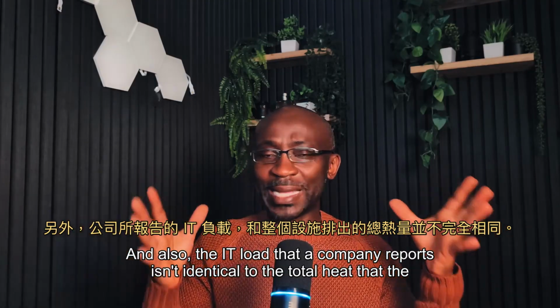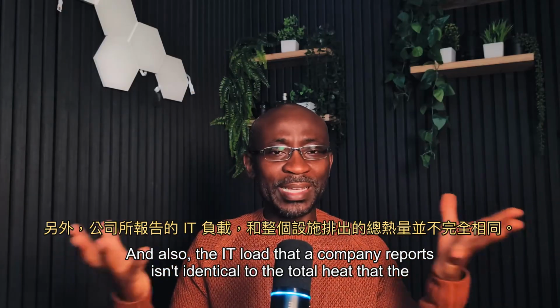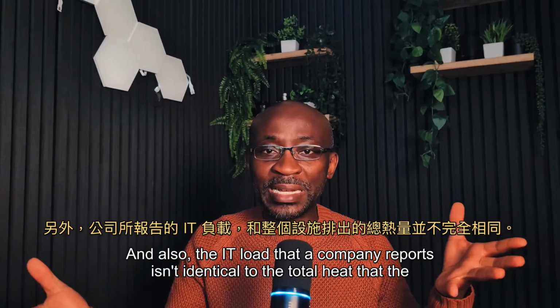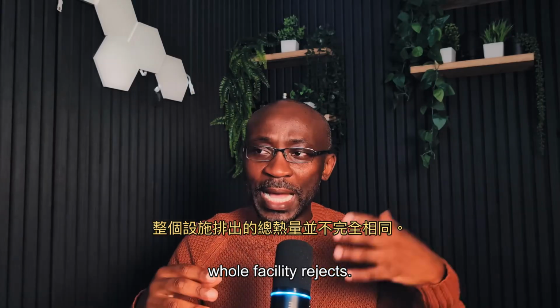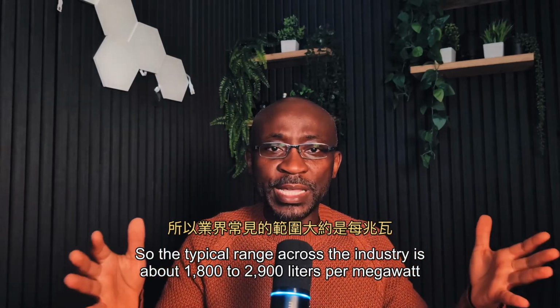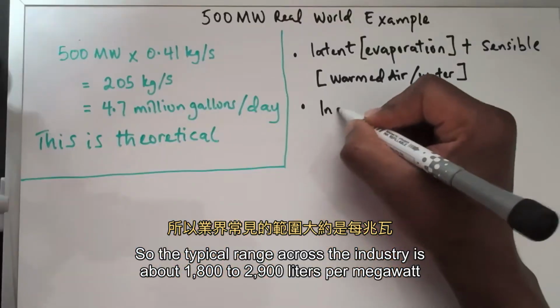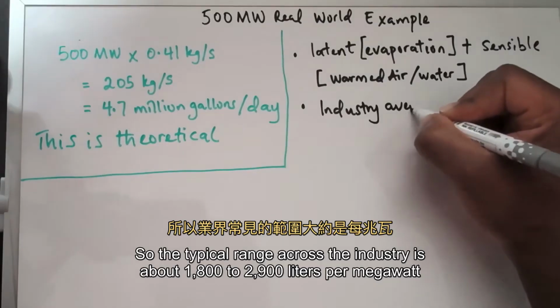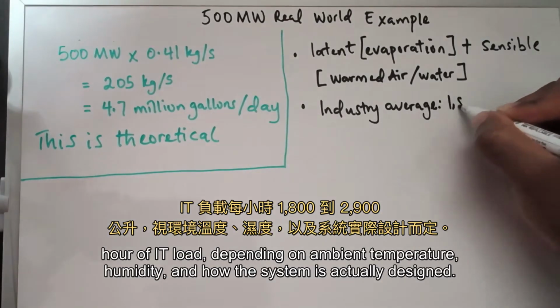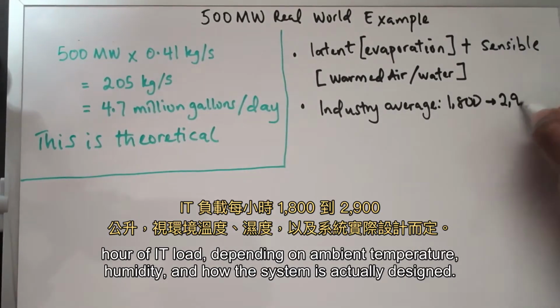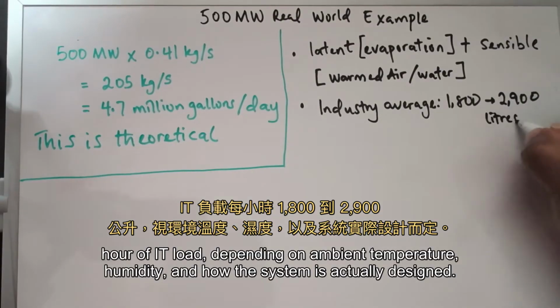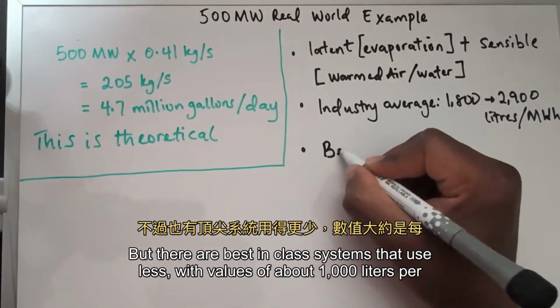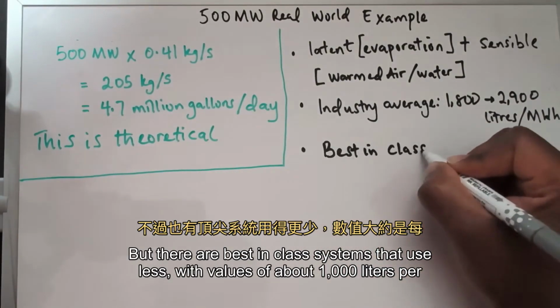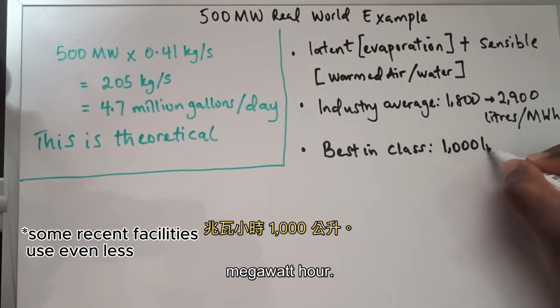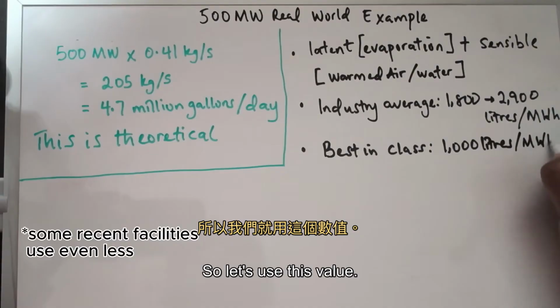And also, the IT load that a company reports isn't identical to the total heat that the whole facility rejects. And so the typical range across the industry is about 1,800 to 2,900 liters per megawatt hour of IT load, depending on ambient temperature, humidity, and how the system is actually designed. But there are best-in-class systems that use less, with values of about 1,000 liters per megawatt hour. So let's use this value.